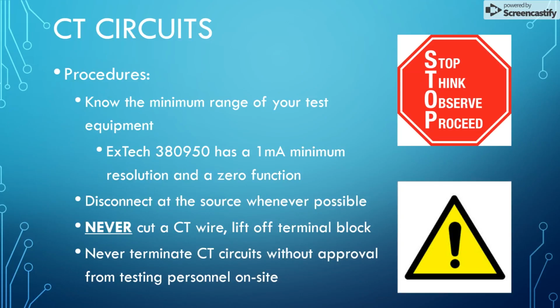Another important thing: when you check to see if your wire is dead before you lift it, you need to know the minimum range of your test equipment. We've had several instances where we've tripped something off because we thought the circuit was dead, only to find out it had a very small value of current that was relevant. The ExTech 380950 amp meter that we give everyone has a 1 milliamp minimum resolution and a zero function, so we need to zero it before we use it and then make sure the circuit is actually dead.